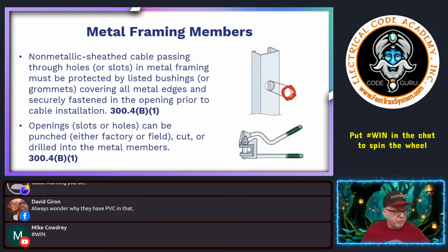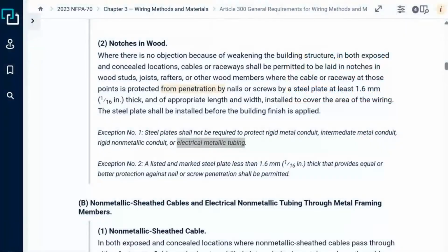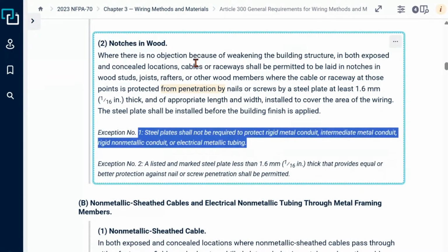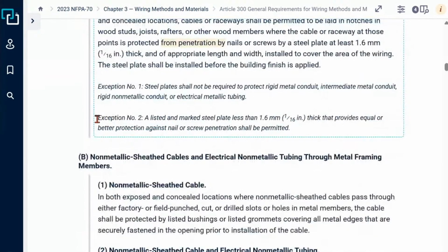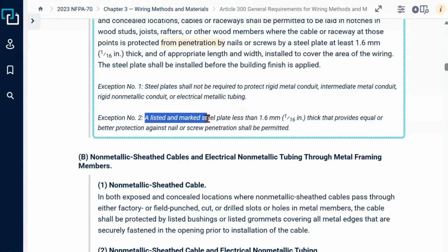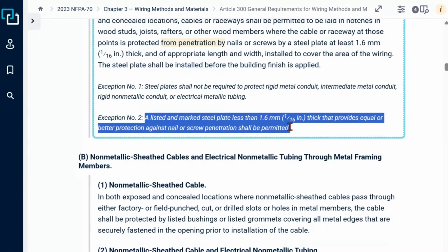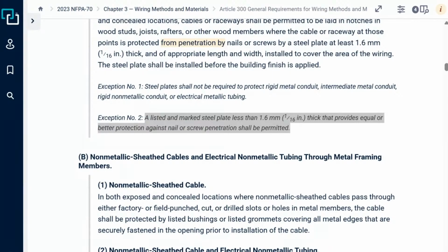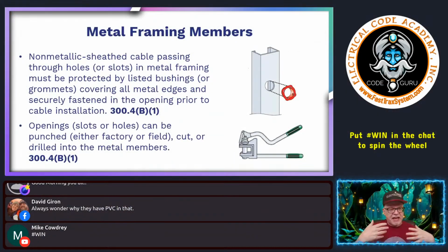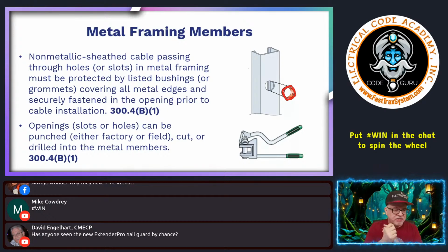All right. So that exception, oh, by the way, I got the other exception. Sorry about that. The other exception, let me get back here. So that is where you don't need the steel plates if you're running through board holes or notches. That's the same for both, by the way. And then, of course, you have exception number 2. And this is where a listed or marked steel plate less than 1/16 of an inch thick that provides equal or better protection against nail or screw penetration shall be permitted. Okay, so you can get nail plates that are listed or they have specific markings on them. They've been designed specifically as a nail plate. Then it may be less than 1/16 of an inch, but that's okay because they're marked, labeled, they're for a specific use. They're okay, that type of thing. All right, okay. And it may also be the listed ones that go inside of the framing members. They may be less, but they may be identified and basically listed and marked for a specific application, okay?